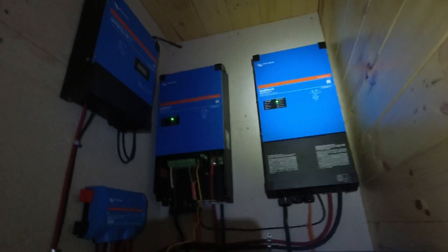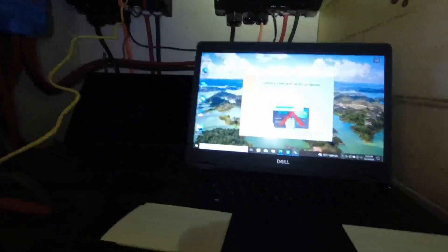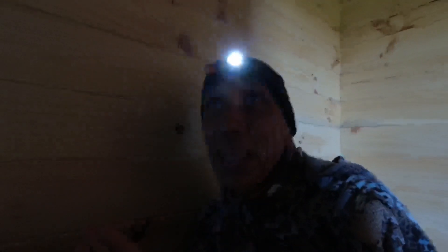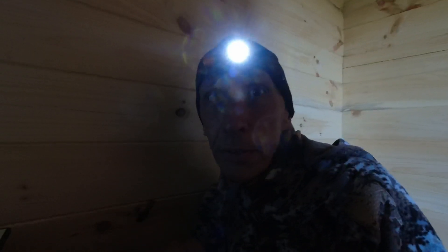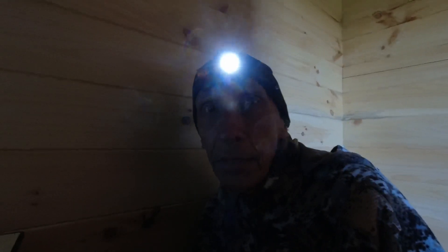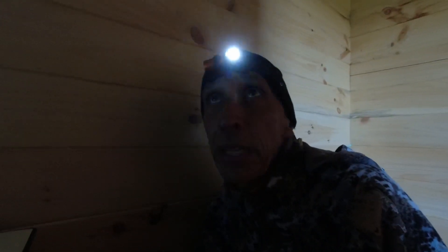While the cabin is being set up, I'm programming the Multi Plus Twos for the inverter that the customer is using, limiting each side to 20 amps. If he uses 240 volts it'll charge on both inverters, but if he uses a Honda EU3000 that only puts out one phase, then only one of these inverters will charge so it will not overload the small generator.